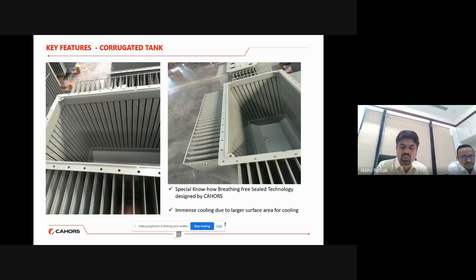So all these processes we are doing in our factory, including the leakage and pressure test of the oil, so that whatever condition happens at site, we bring that condition into the factory and we test every tank before oil filling and after oil filling. Every transformer is tested independently so that no surprises are faced by the customer at site. So this is the technological advancement and core expertise that we have in the sealed type of transformer.